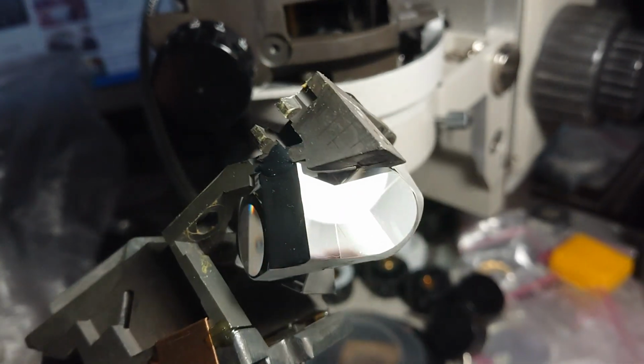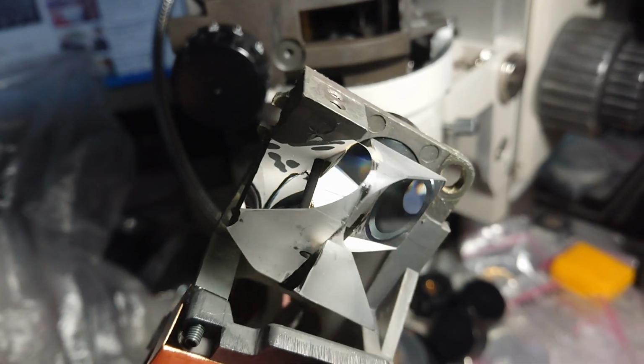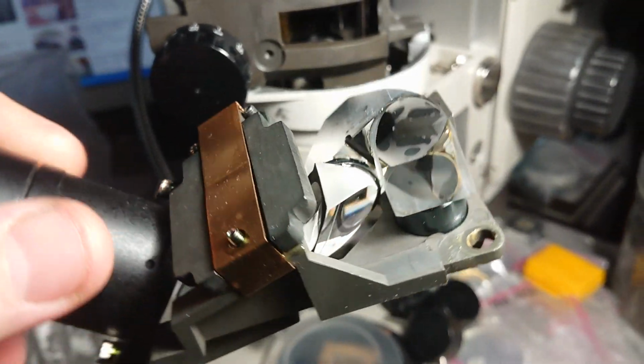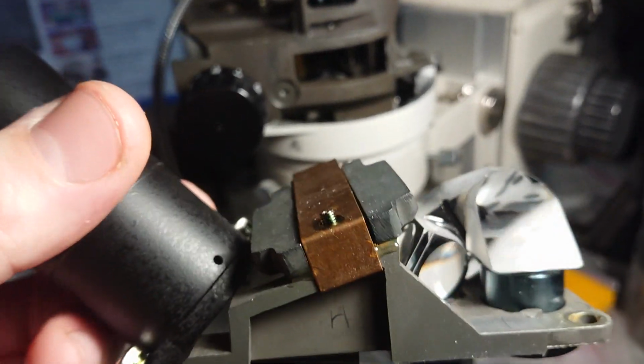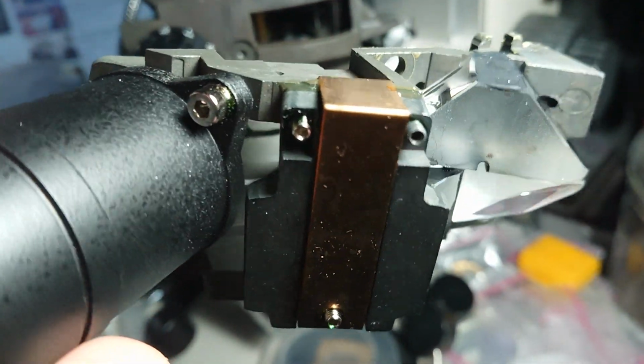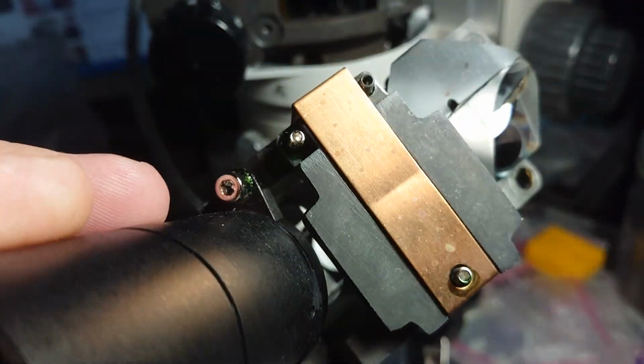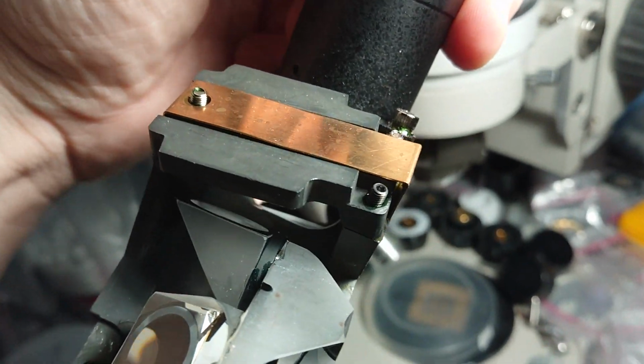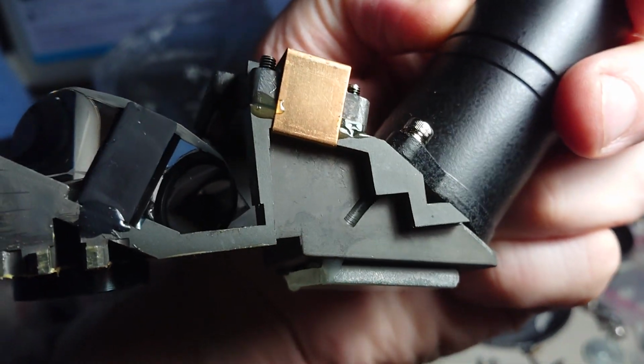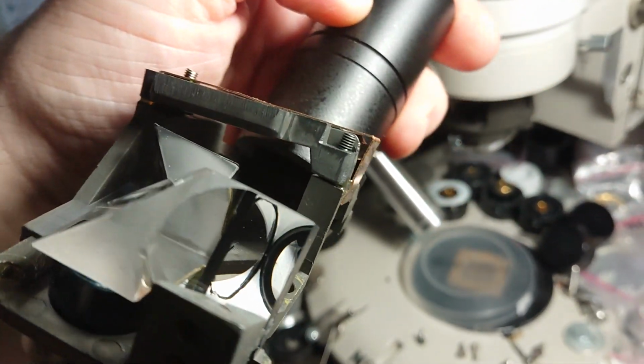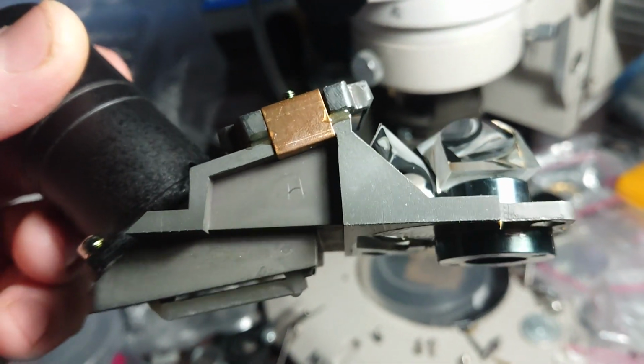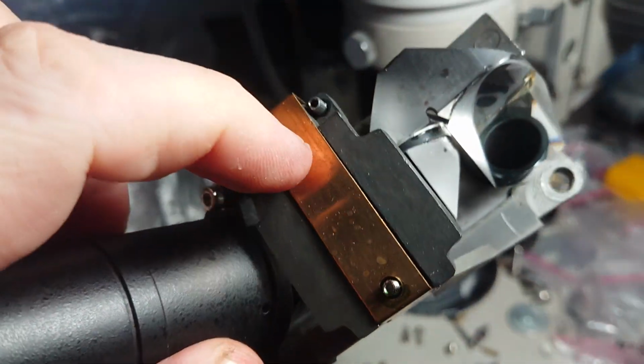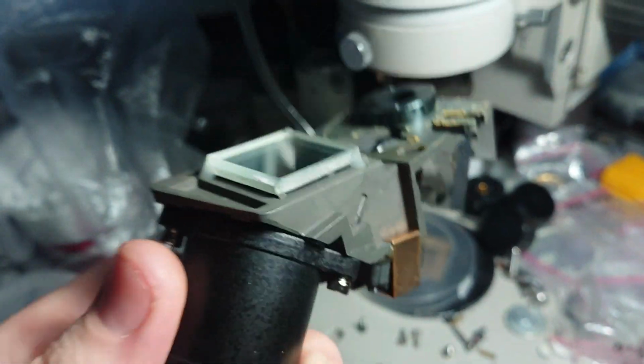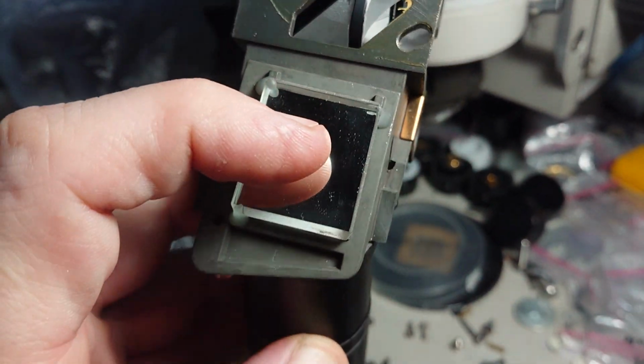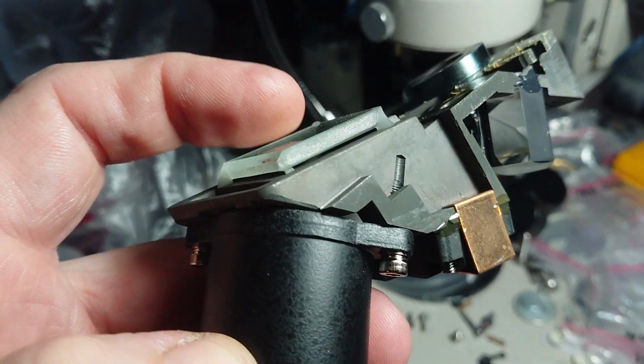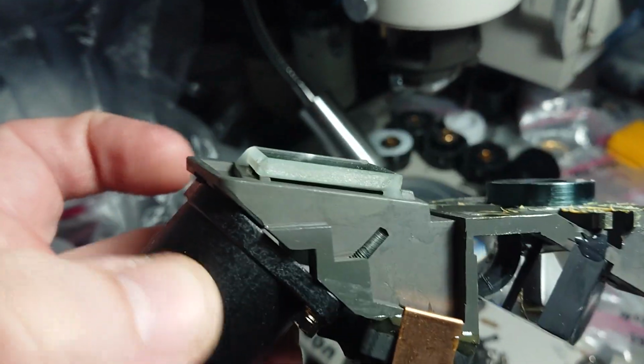You can see that these three glued prisms are pretty tiny compared to the Olympus SZ61, but the mirror is made in a bit different manner. We have three micro adjustment screws here, some copper-like springing plate, so we can make some adjustment here. The bottom glass is just glued, no possibility to make corrections.